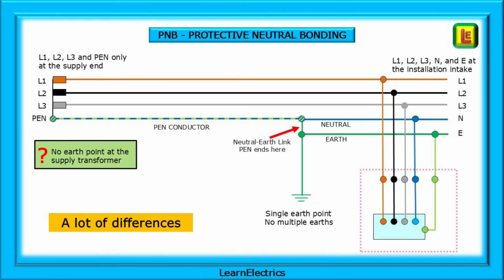The PEN conductor, along with the phases, will travel towards the installation. At or near the installation, ideally within 40 metres, a neutral to earth link will be made and an earth rod installed. At this point, the PEN conductor will be split into a separate neutral and a separate earth. This will be the only earth point for this earthing system type, a single earth point and no multiple earths.